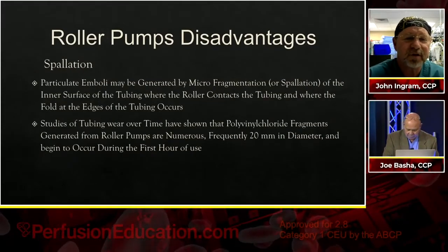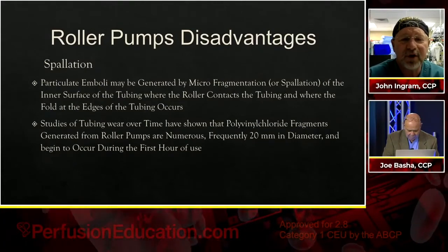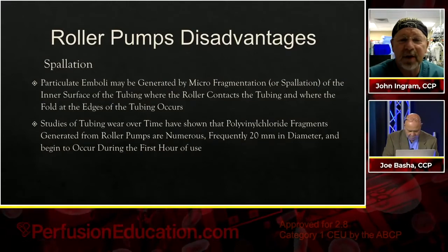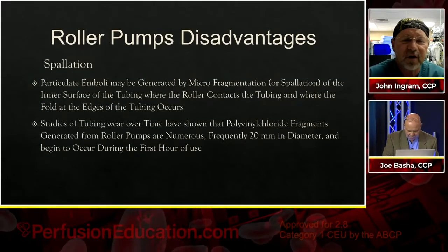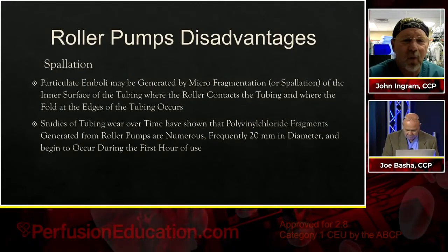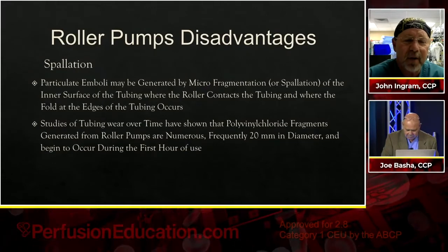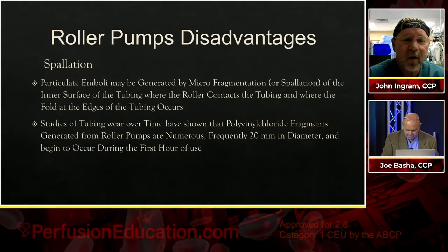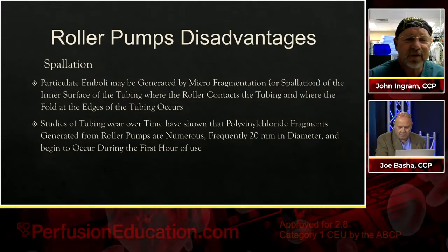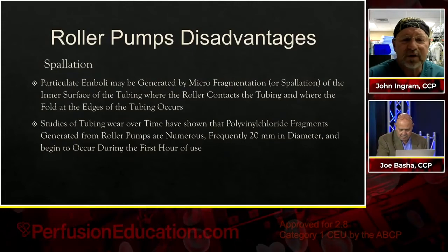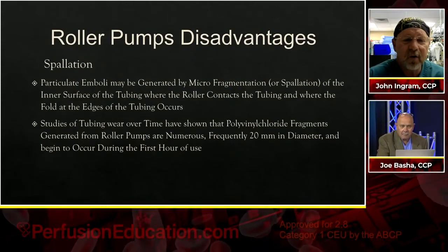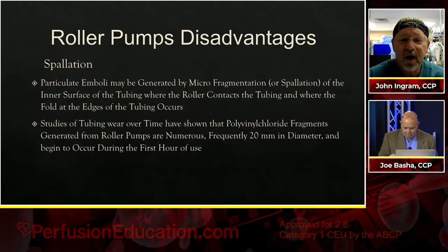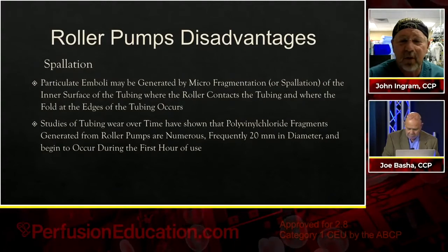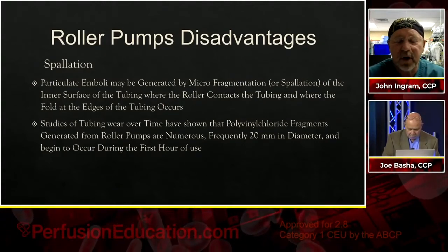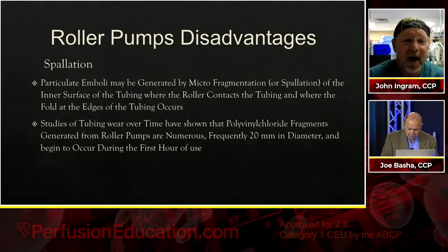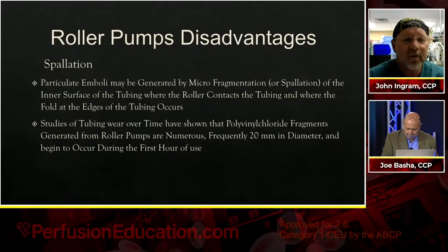Yeah, spallation. Another disadvantage of roller pump is that particulate emboli may be generated by microfragmentation, called spallation, of the inner surface of the tubing where the roller contacts the tubing and where the fold at the edges, the top and bottom of the tubing, where the tubing fold occurs. You can have the spallation, okay? Studies of tubing wear over time have shown that polyvinylchloride fragments generated from roller pumps are actually quite numerous and frequently as large as 20 millimeters in diameter, which sounds pretty scary. That would never make it past your arterial line filter, thankfully. But they actually begin to occur as early as in the first hour of use.